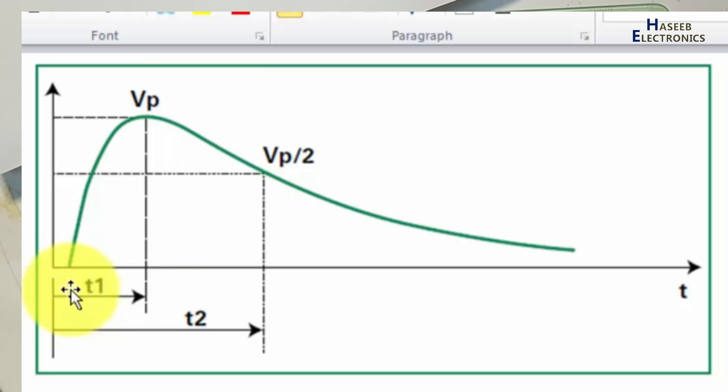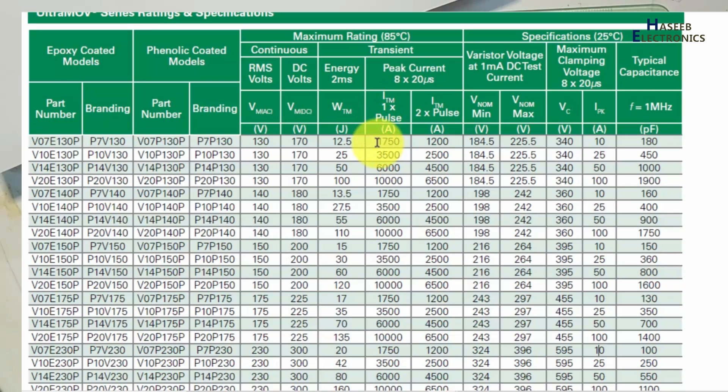After 8 microseconds, if the pulse remains high up to 50 percent of its peak, this time will cover from t0 to 50 percent - that is 20 microseconds. 8 microseconds for rising, 12 microseconds for falling. It is called 8 by 20 or 8 over 20.